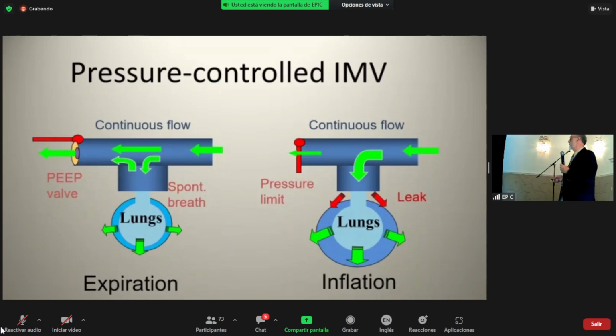And then when the ventilator cycles on, the expiratory valve closes, the circuit's pressurized, and gas flow is diverted into the patient's lungs. And the volume that enters the lungs is a function of the positive pressure within the circuit and the compliance of the lungs. That's the basic functionality of pressure controlled ventilation. And the problem of leak around the endotracheal tube doesn't really exist because there's plenty of fresh gas flow available. Excess gas overflows over the pressure limiting valve. So we don't care if there's a large leak. And it was the ease with which you could ventilate babies with large endotracheal tube leaks, and the conviction that pressure is the bad guy, pressure is the cause of all ills, and we like to control it, that led us all to use pressure controlled ventilation.